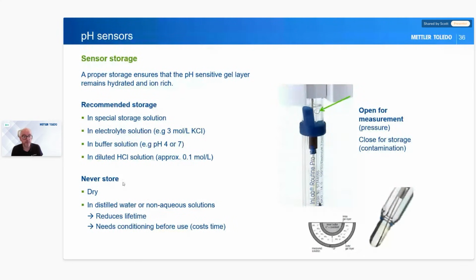So things we never do. We never store the electrode dry. If we store it dry, what happens is that gel layer at the bottom here, on the end of the bulb, becomes dried, it shrinks and then pulls away from the glass. If it pulls away from the glass, you don't have the contact to allow the hydronium ions in and out. So we must make sure that we store it wet, or hydrated, all the time, so in some sort of solution.